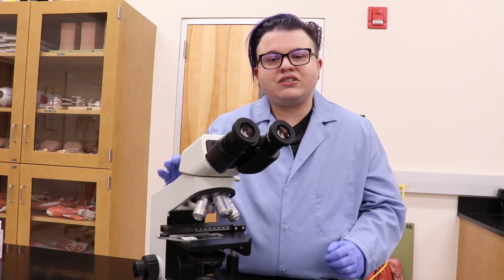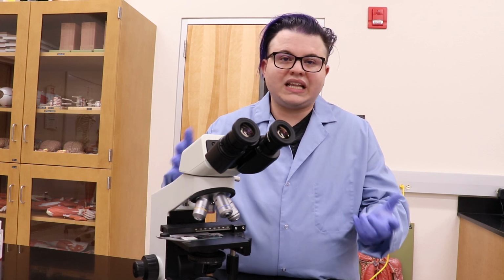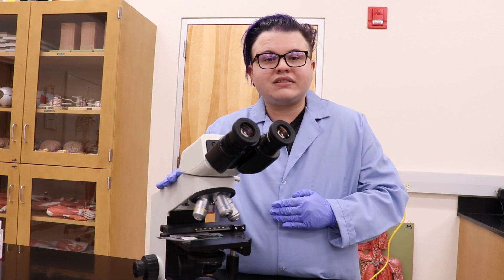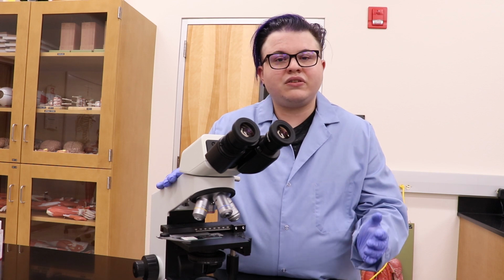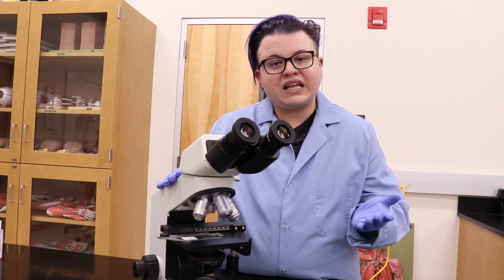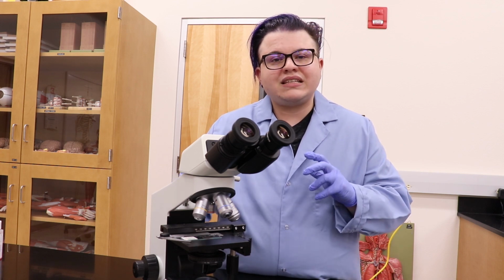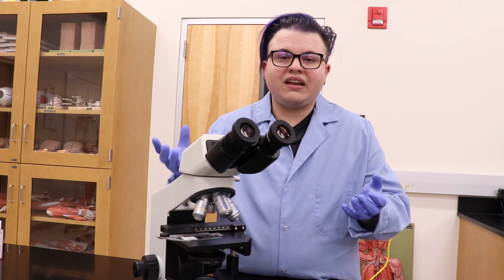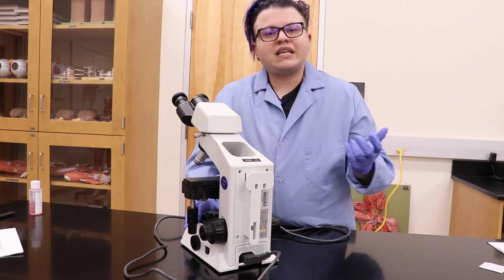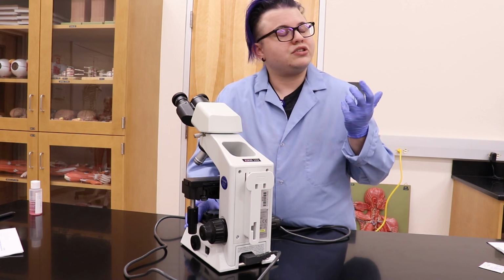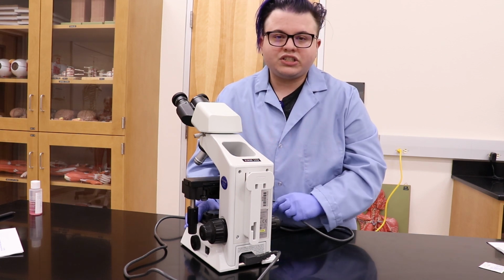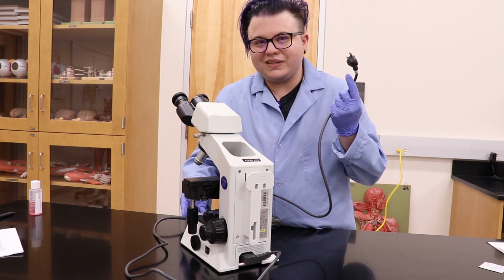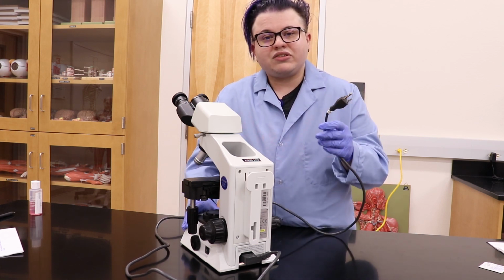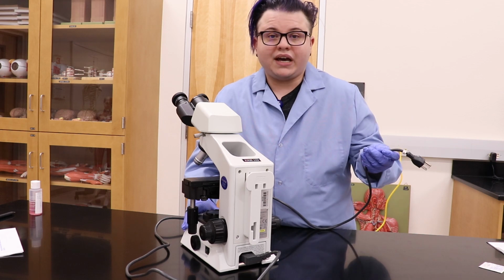Next, we'll be moving on to troubleshooting some problems in class. Now, you might come across problems that you can't handle due to the time constraints that you face in a classroom, but here are some things that you might be able to address instead of bringing a microscope to a staff member. If the student is having problems with the microscope not turning on, one thing that you might want to check is to make sure it's plugged in. This one is obviously not. And make sure that the outlet that it's in is actually powered.